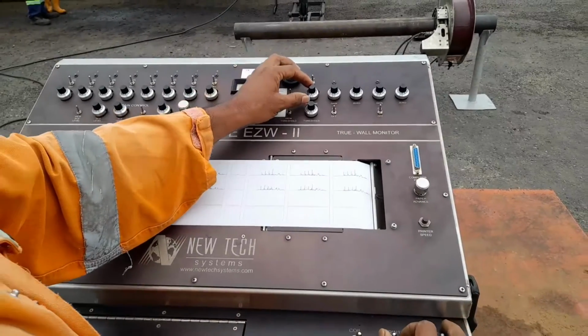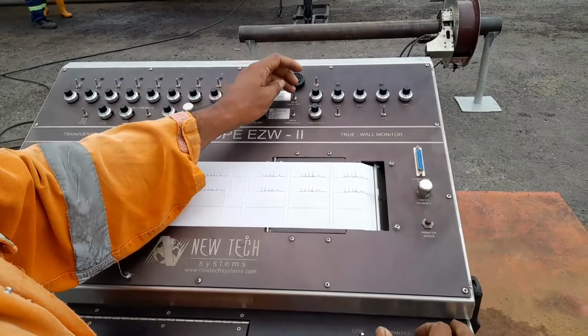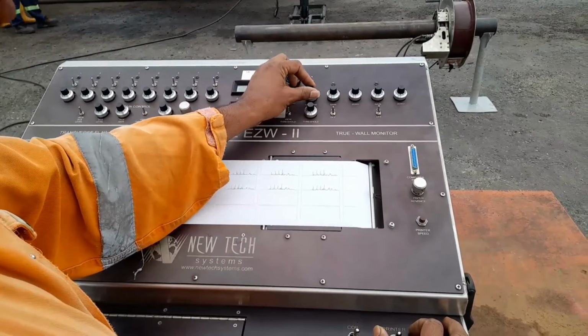Next is the third method, a very easy method. I am always following this method, the third one. Initial setup is all the same. Adjust the baseline and the threshold: the baseline on 1 or 2 mm from top, the threshold on 10 mm or 5 mm from bottom. Switch on the mag, give a certain value to zero, 1 or 2. That depends on the pipe.